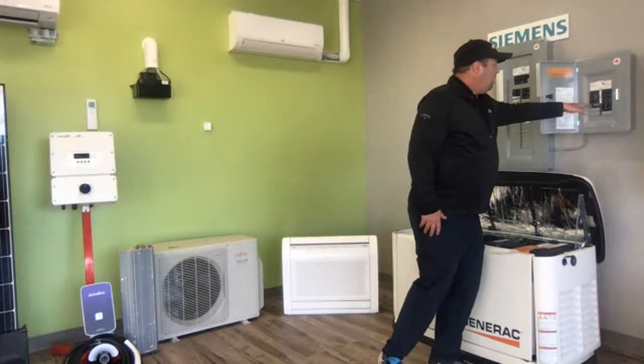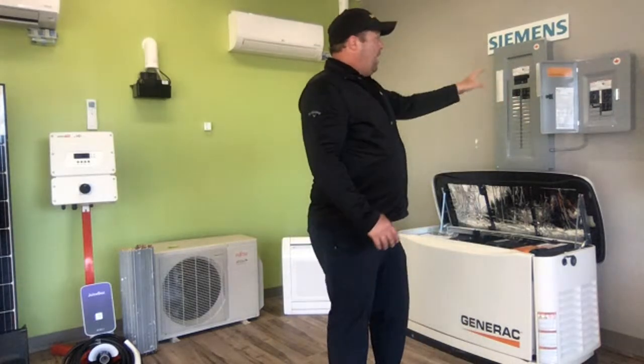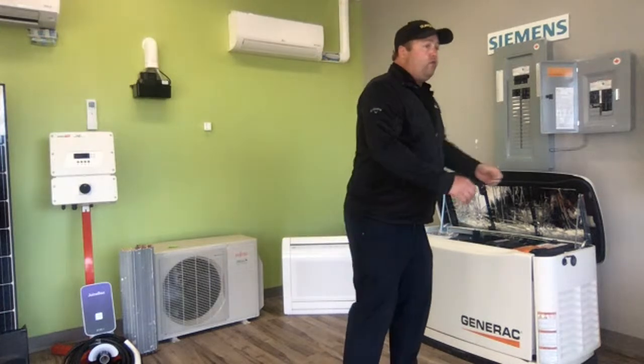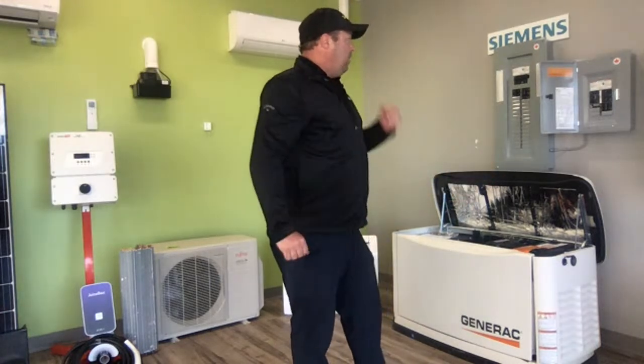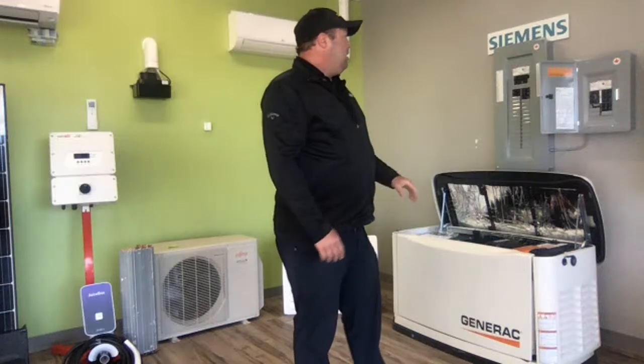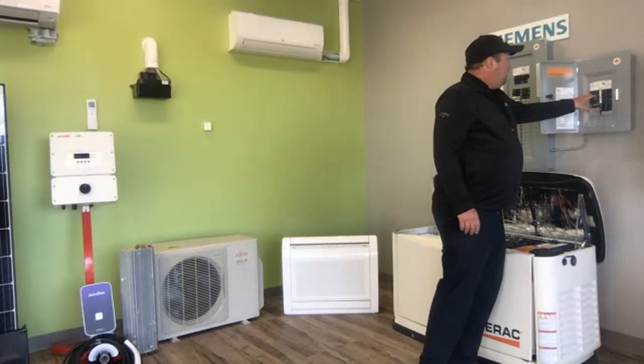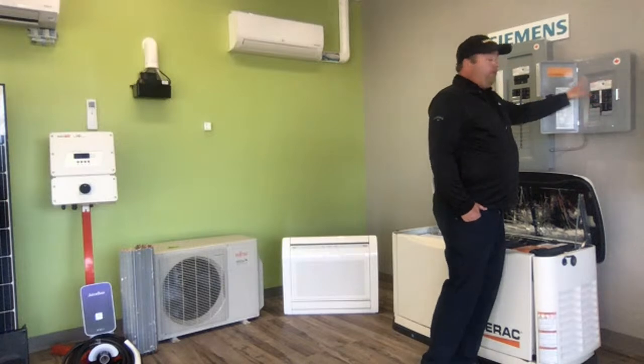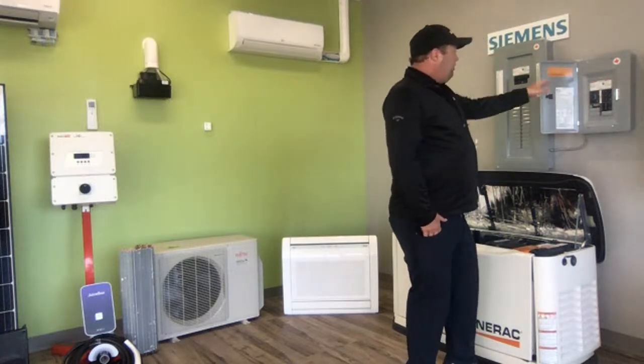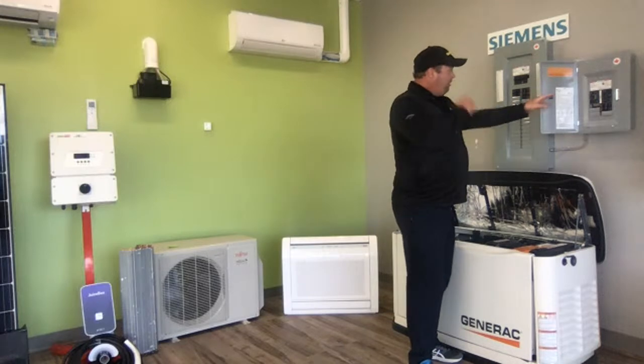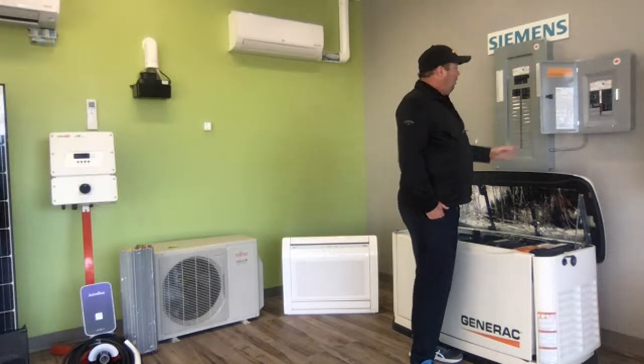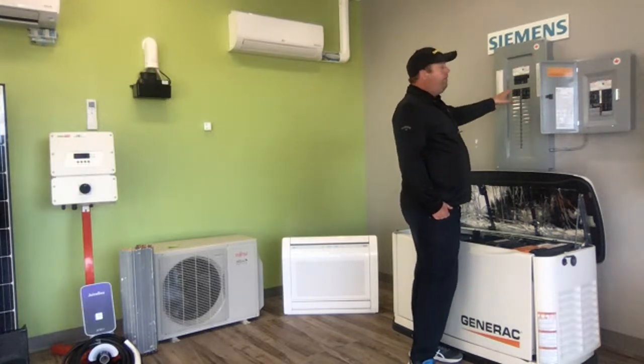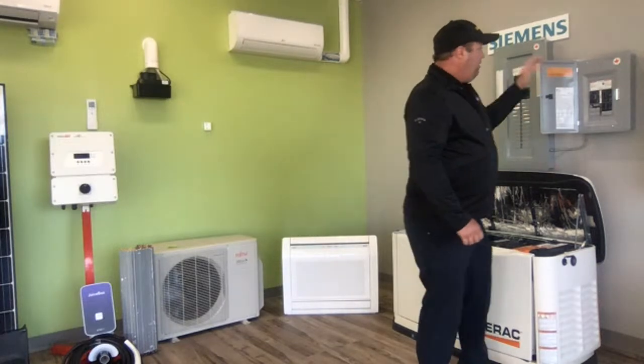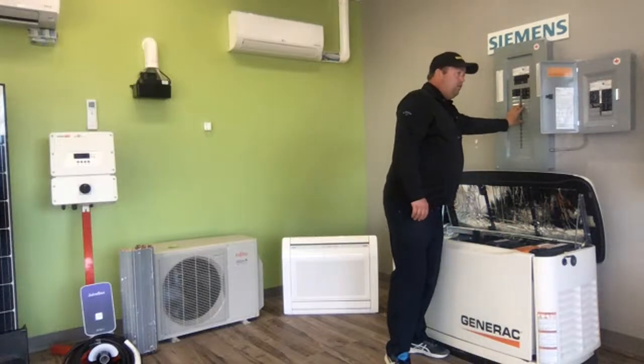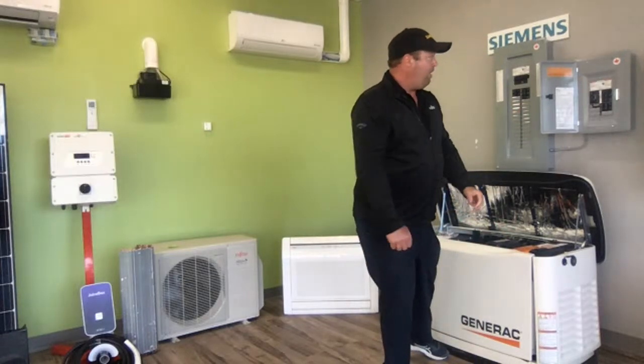This solution here is something you can do, where you take your own portable gas generator that you fire up with a cord or even a press button, and that feeds this panel. You're required to have this panel if you run a generator, because this generator panel will isolate itself from the main panel.